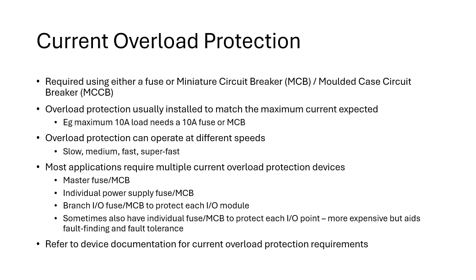And to do that, we use fuses or miniature circuit breakers. So for example, you might have 10 amps coming out of a power supply, but what you might want to do is protect an input module which may have a rating of 1 amp. So you might use a 1 amp fuse or MCB for that particular input module. Now, what we do with overload protection is, based on the current rating, we normally size the overload protection to match that maximum current expected.